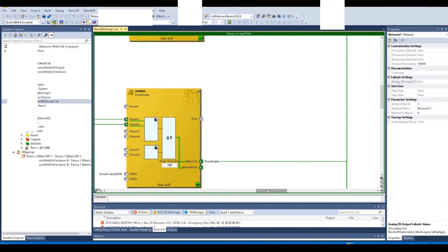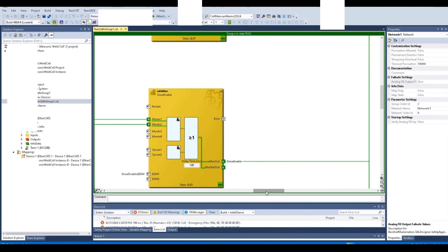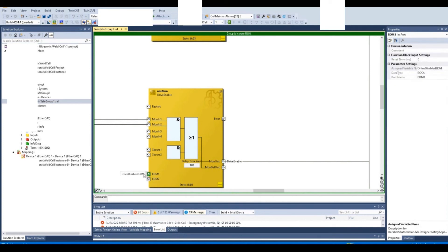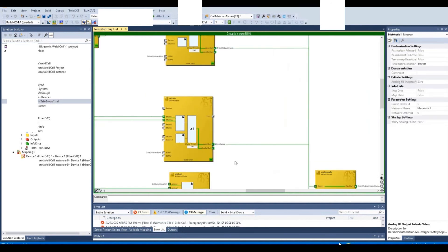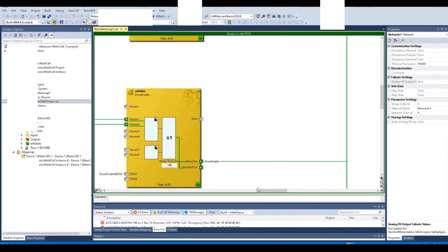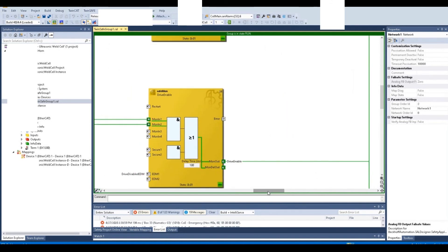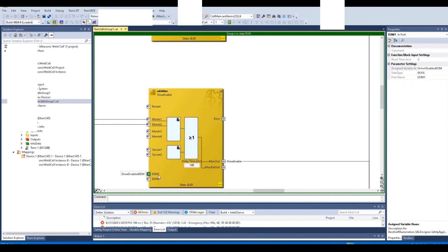Let's watch this process. Now it's on — command goes off, function block turns yellow, so the EDM is on. With the EDM on already, once the command goes on, the drive enable will turn on; after this, the EDM signal will go off as feedback. Let's watch it again: in normal status, EDM is off. Command goes off — EDM turns on, getting ready for next time, function block turns yellow. Command on — drive enable is on, EDM signal goes off after.